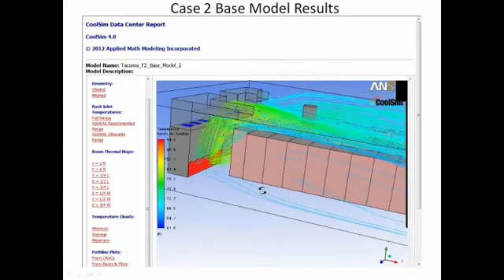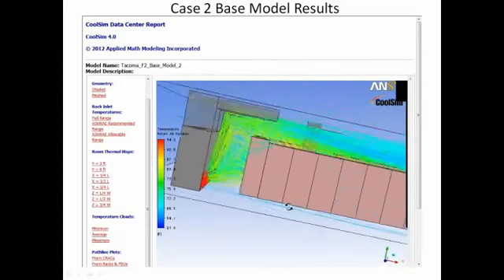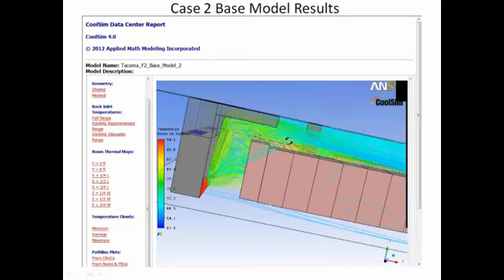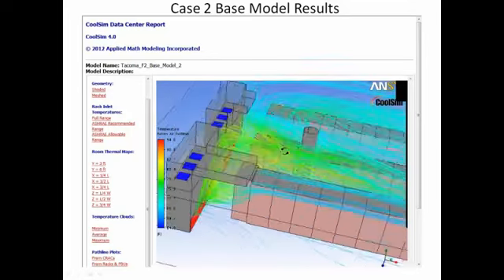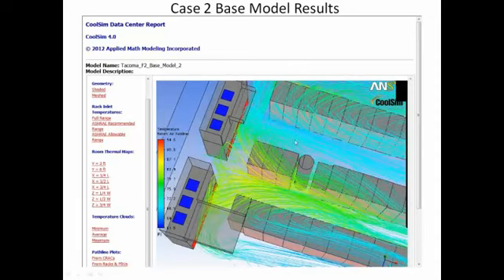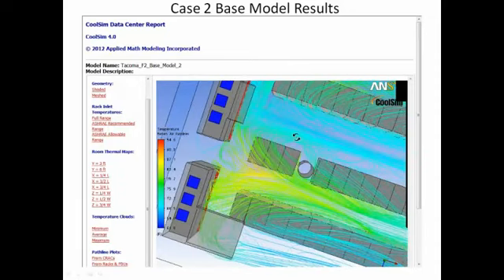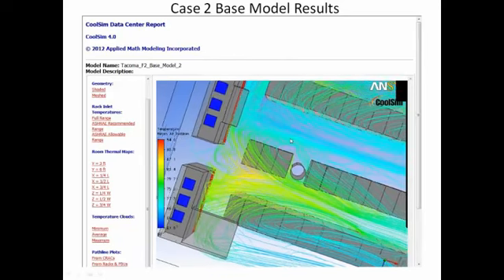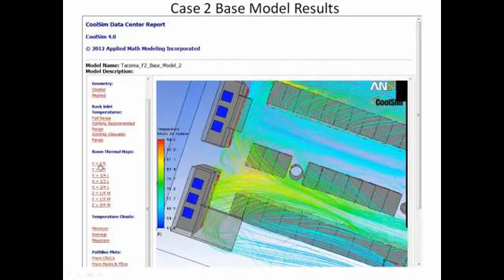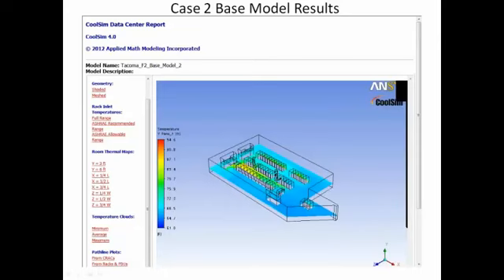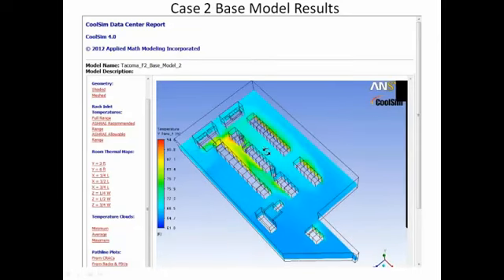If I turn this model around and look at it, you see what's happening. The hot air is moving up because it's hot, so it's buoyant. The buoyancy is causing the air to rise. It's mixing with that cold air that's shooting out, and then it starts to come down and get sucked into those returns. But during the intake to the return, it's going right by the rack inlets, and it's changing the temperature there. So if we were to look at a cut plane here at 3 feet, we would see quite a bit of color variation there.